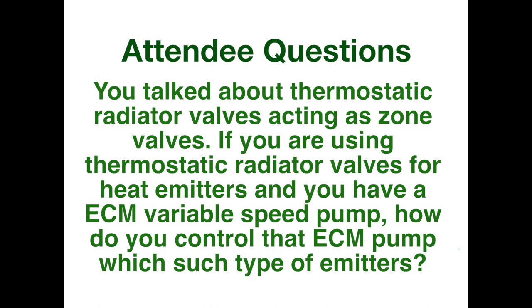So that's one way. The thermostatic radiator valve opens, the pump wakes up and says, okay, now who's going to make the boiler come on? There is no wiring interaction between that valve and the pump. So as the pump starts to rev up, that little induction relay trips on the boiler. Now, Cody, I think you had another, like a central thermostat option too.